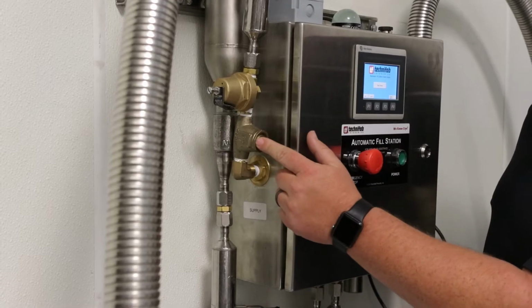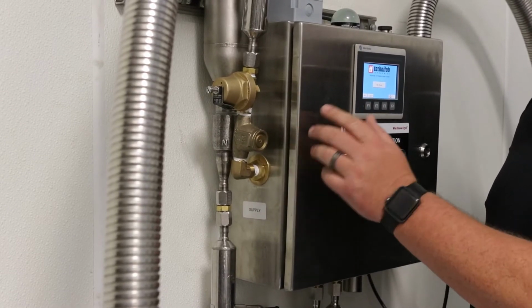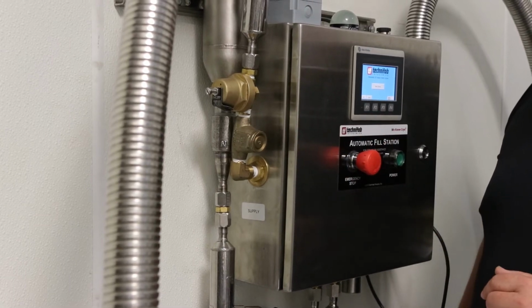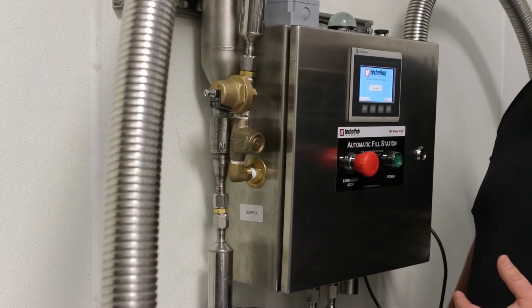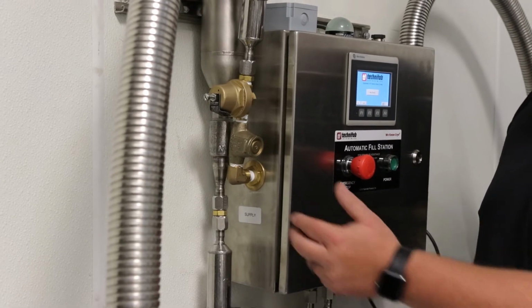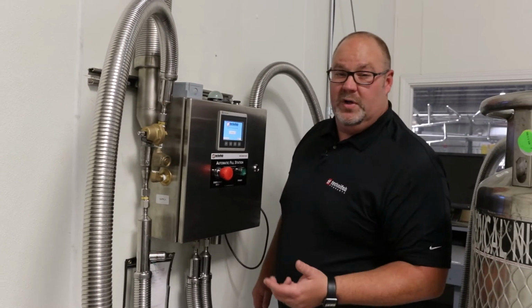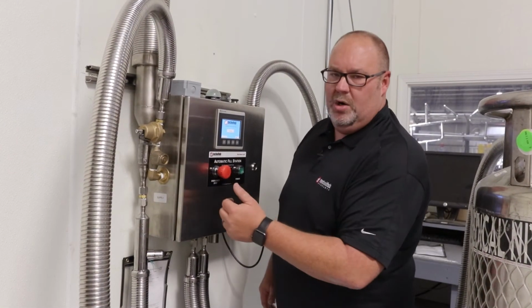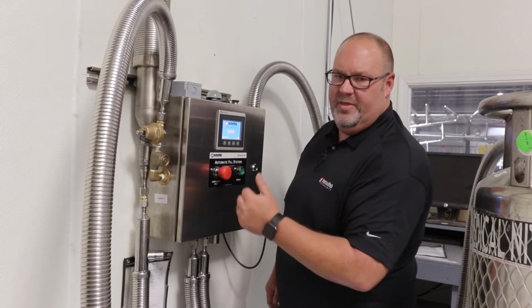We also have a strainer. We strongly recommend a strainer. The inside of the unit does use cryogenic solenoid valves, and debris can cause problems with those solenoid valves, so we strongly recommend either a filter at your bulk tank or a strainer that we will supply with the unit.